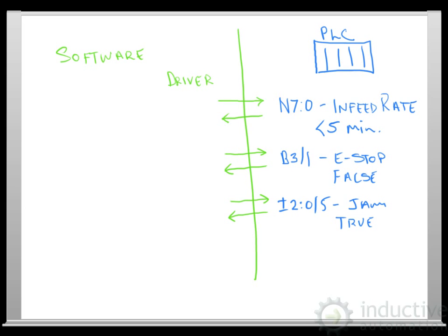It cannot request all these at the same time. It has to request them one at a time. Some PLCs allow multiple requests at the same time, but again, there's no guarantee of how it's going to group those requests to get those values back at the same time. And herein lies the problem. So if we take a look at this on a timeline, we'll make this real simple for the discussion. We'll use relative time, and we'll also use seconds. In reality, it's probably milliseconds.